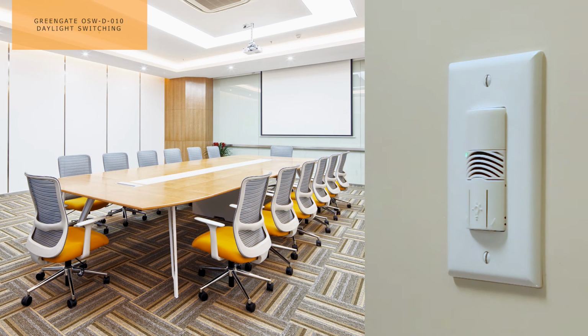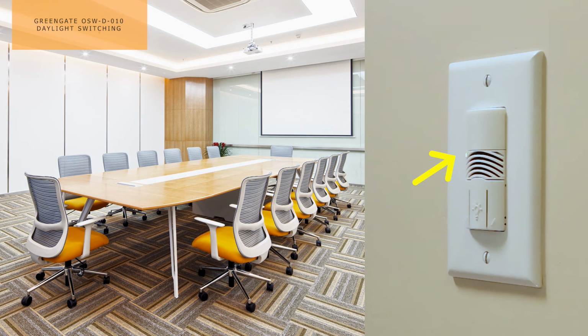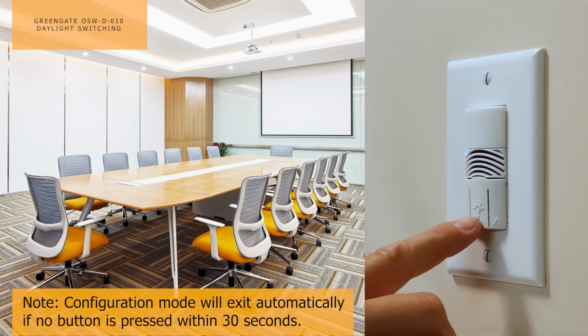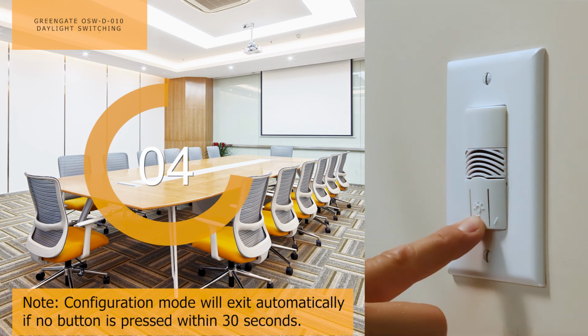To save the calibrated setting, press and hold the OnOff button for 3 seconds until the yellow LED starts to flash. The LED will flash 13 times and then return to configuration mode. Manually exit configuration mode by pressing and holding the OnOff button for 5 seconds.